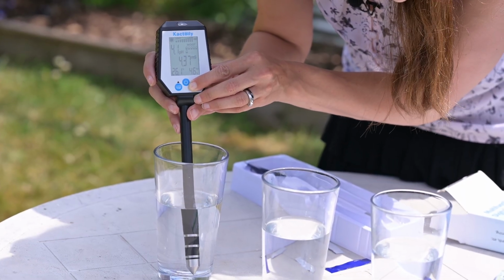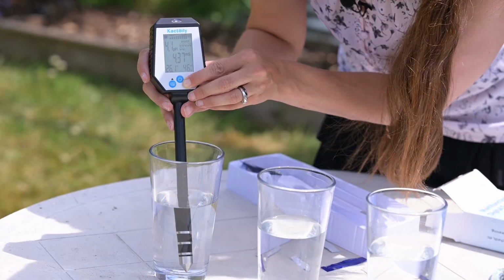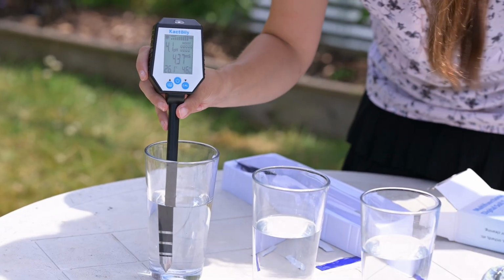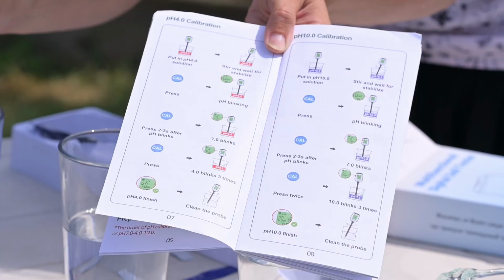No. It's hard work not working. And then 7.0 should blink. That's what it says. You can see right there. After you press calibrate, pH blinking, which it does. So then you press 2 to 3 seconds is what I'm interpreting.